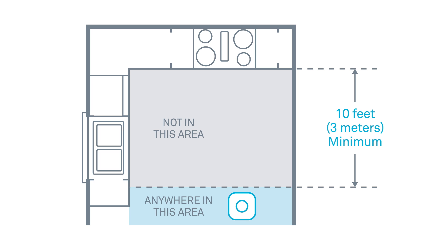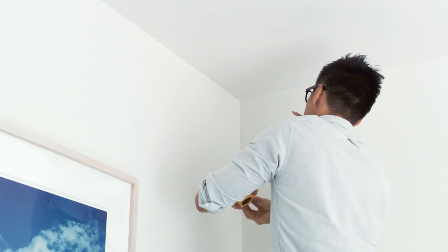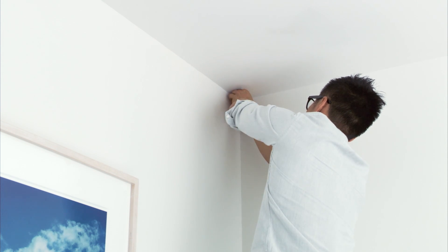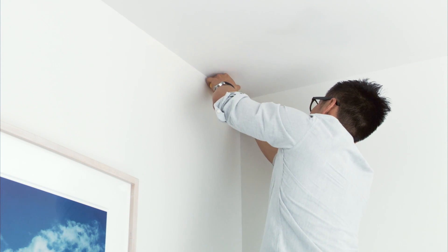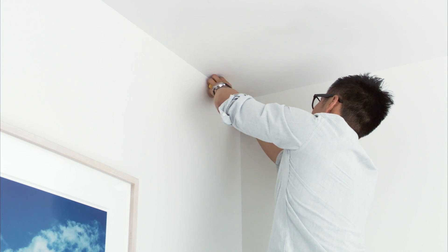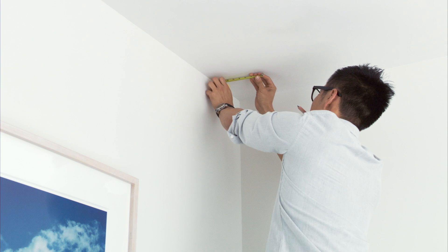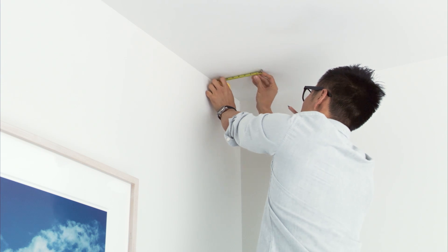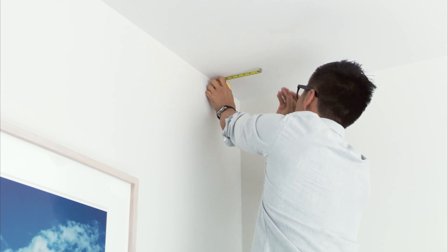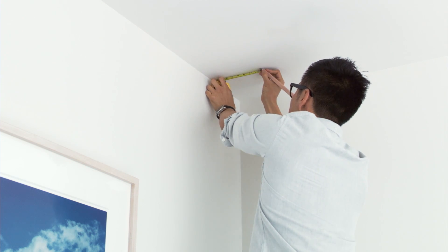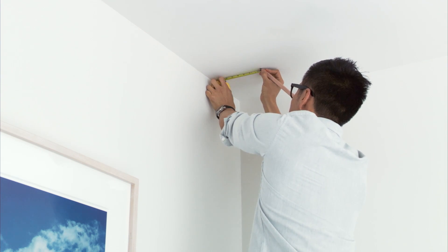Make sure it's at least 10 feet or 3 meters away from cooking appliances. If you're replacing an old smoke alarm, you can probably install Nest Protect in the same place. However, it should be at least 4 inches or 10 centimeters from the ceiling or wall.